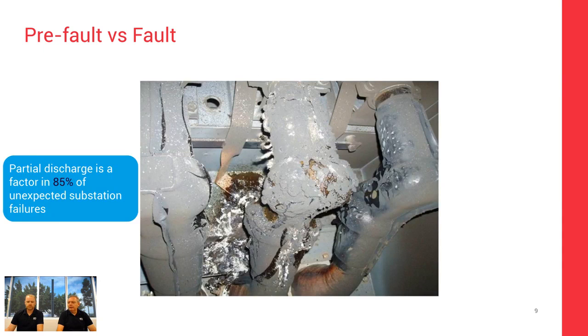But at the same time, if we let that happen, as you can see here, is exactly what happened. Now the switchgear has disruptively failed. So at this point, we're not in the situation where we're in control. This failure has happened wherever it may be, usually 4 o'clock in the morning on a Saturday or something. You've got overtime. You've got unexpected switching to do, lost production, or lost elements of the network. We've got the carbon generated from the fault area now. So that carbon, the dust, the debris has now gone up the bus bar. So it's affected larger components, maybe down into the CT chamber, down to the circuit breaker, and the cable box, depending on the configuration of the switchgear.